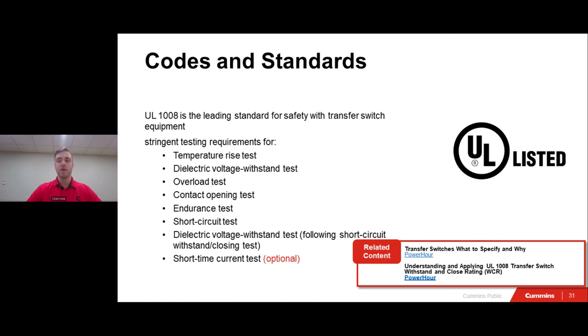And then next up, we have UL 1008. So the second and last code I will highlight is UL 1008. This is the standard of safety when it comes to automatic transfer switches and many other things in life. UL tells the manufacturer what is expected of the transfer switch for performance and safety. This is all accomplished by stringent testing, and some of those tests include, but are not limited to, temperature rise test, overload test, endurance test, short circuit testing, and more.